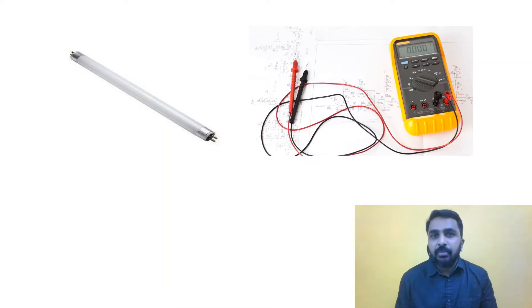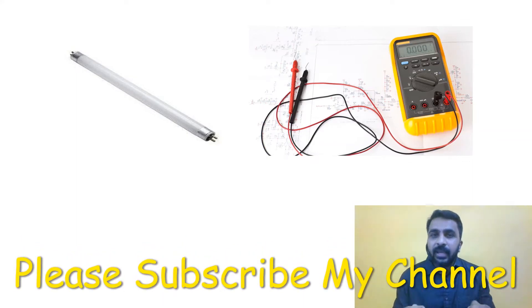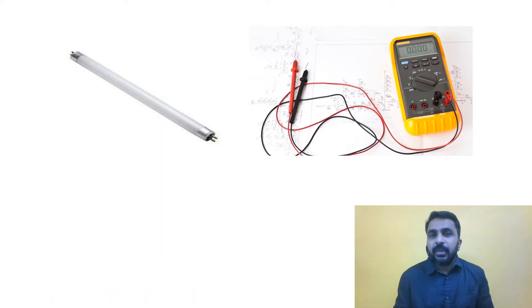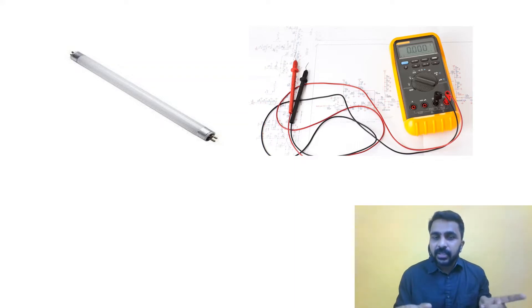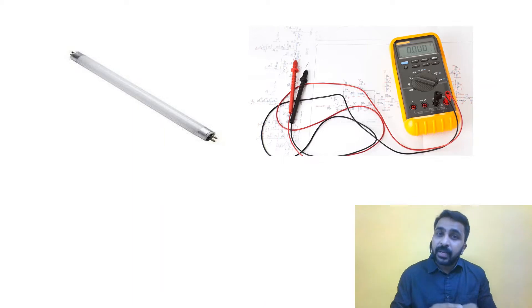Turn the multimeter to continuity mode. When you touch the red and black probes together, you will get a small buzzer sound, which means the multimeter is working. Now take the red and black terminals and connect them to one end of the tube light — it has two terminals. If you hear a sound, one side is working. Then check the other end. If you get continuity there too, the tube light is fine — the problem may be in the choke, low voltage, or wiring continuity.